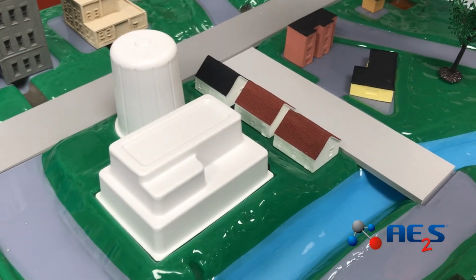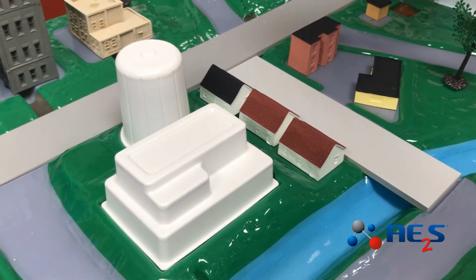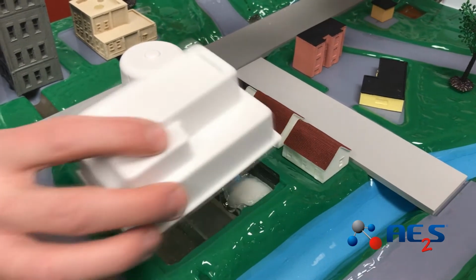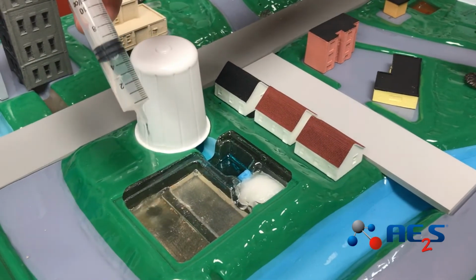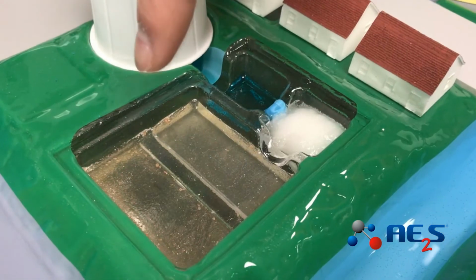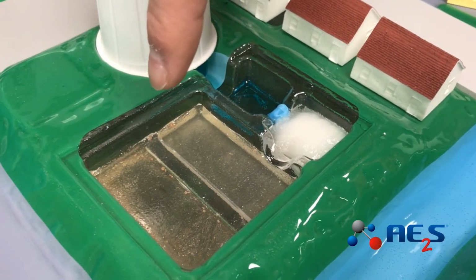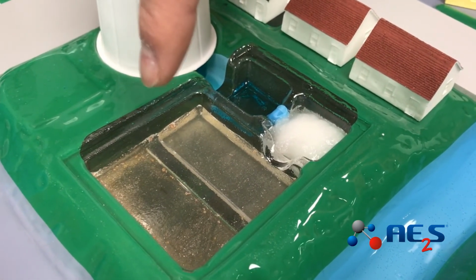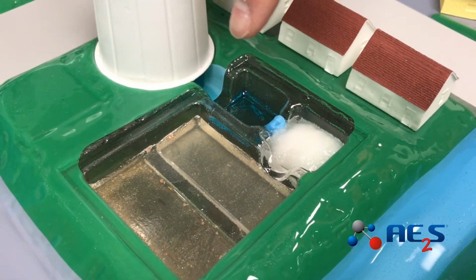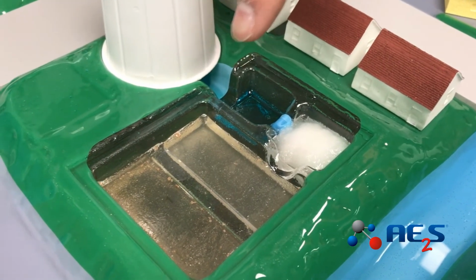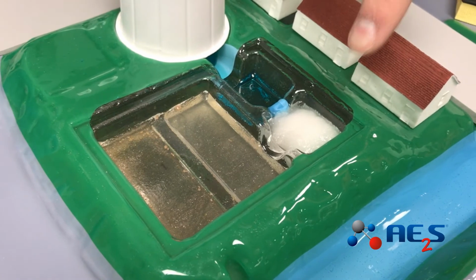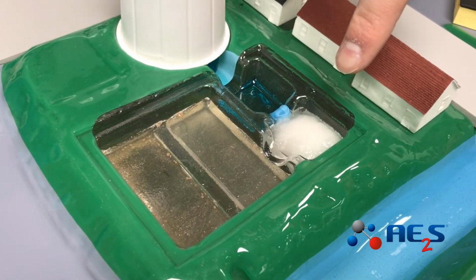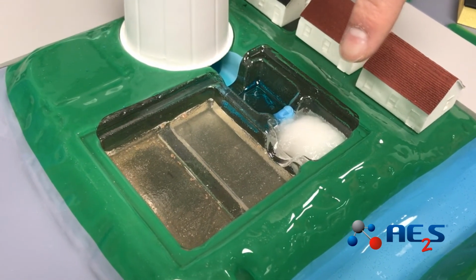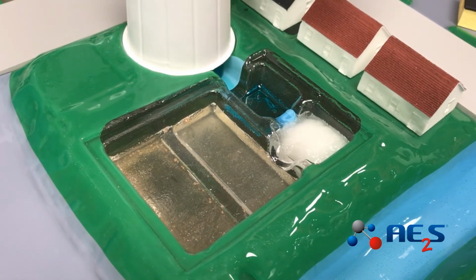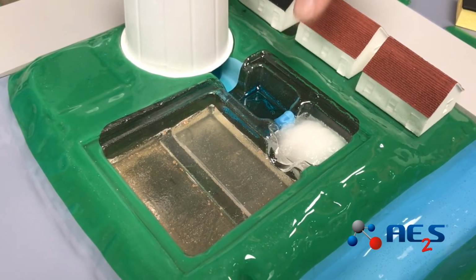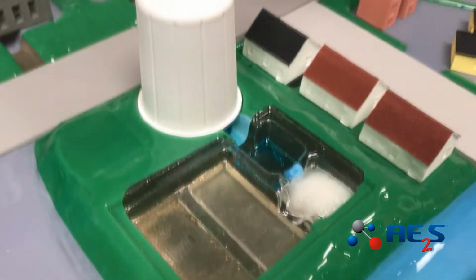Once the water's in the river or a groundwater well, water utilities typically transfer water then to their water treatment plants. The first basin represents the pretreatment basin, typically where solids will settle out with the addition of chemical coagulants. The second basin is the softening basin, followed by a restabilization basin, and the third here with a filtration basin. Following filtration, the clean water is then disinfected and sent to the water tower for water storage.